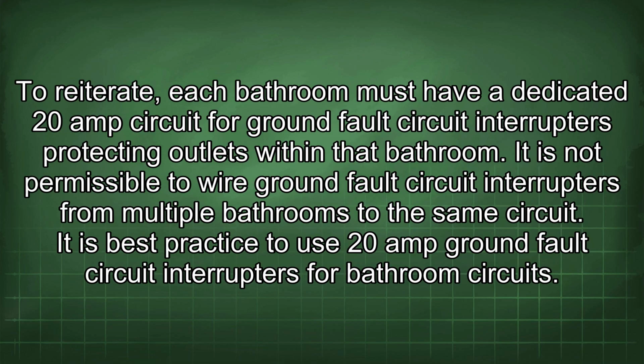To reiterate, each bathroom must have a dedicated 20 amp circuit for ground fault circuit interrupters protecting outlets within that bathroom. It is not permissible to wire ground fault circuit interrupters from multiple bathrooms to the same circuit. It is best practice to use 20 amp ground fault circuit interrupters for bathroom circuits.